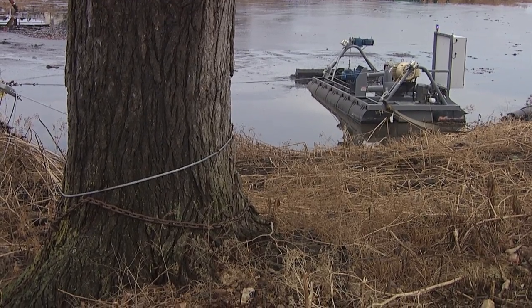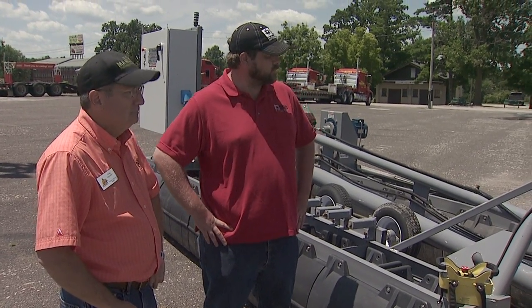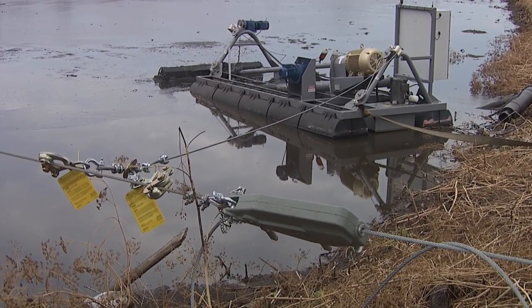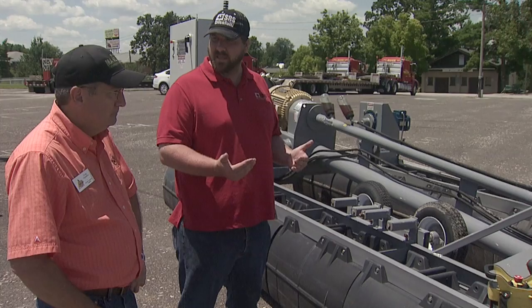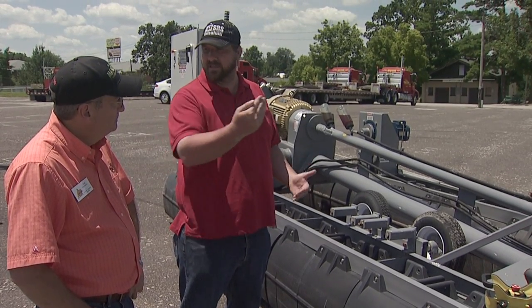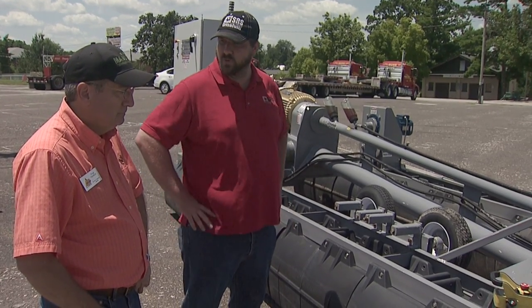So how does it crawl across the lagoon? Is it self-propelled or do you pull it with a cable? We use what's called a cable traverse system. We have a traversing winch on board and it pulls along a cable. We found that's very useful because it keeps you in a very organized, grid-like manner — you know which areas you've covered and which areas you're moving to, so you don't miss any spots.